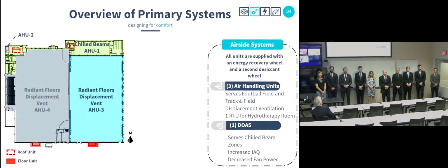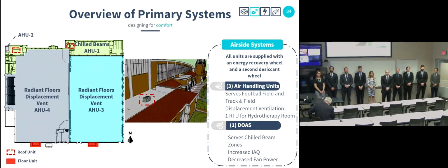The building is served by 4 air handling units that serve conditioned air to the spaces. AHU-1 serves the chilled beam areas on the north side and northwest corner of the building. This unit supplies dry dehumidified air to these spaces to account for the latent and ventilation loads. AHU-2 is a dedicated dehumidification unit that serves just the hydrotherapy pool. These 2 units are located on the low roof section on the north side of the building, but are concealed from view of pedestrians by the sloped roof. AHUs 3 and 4 serve the football field and track and field respectively. They are housed in the AHU units at the south side of the building.